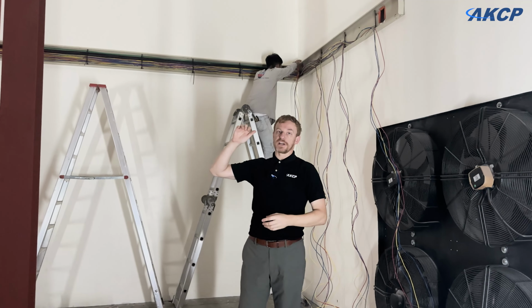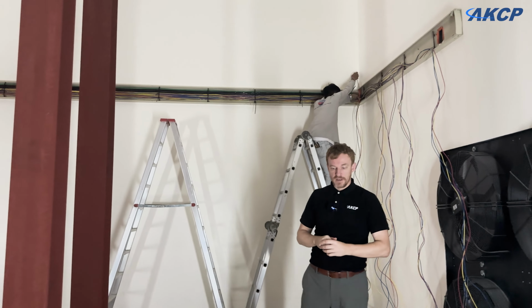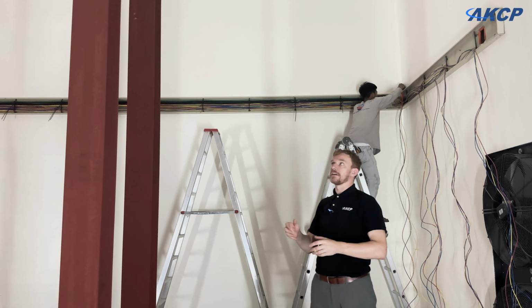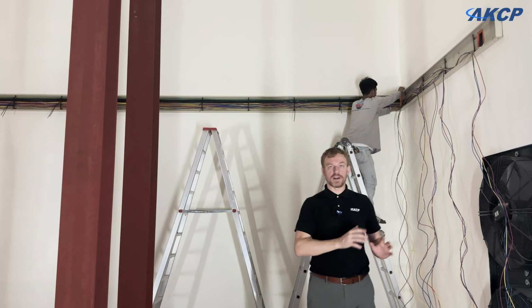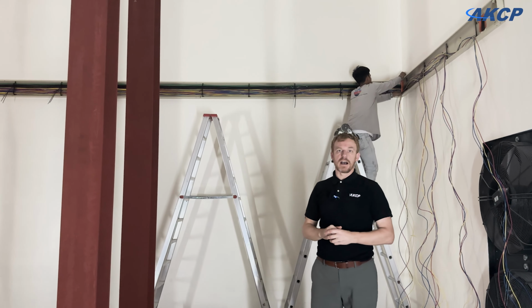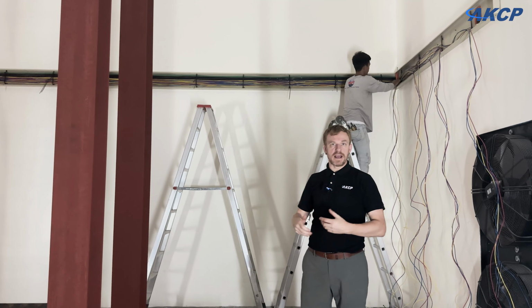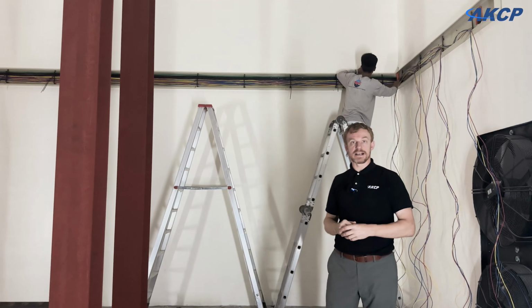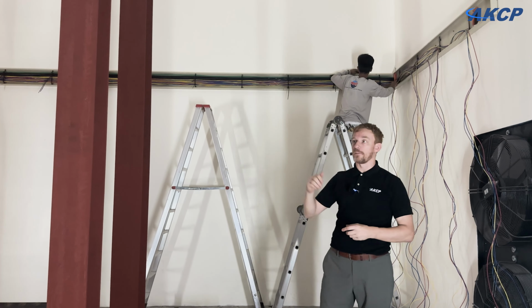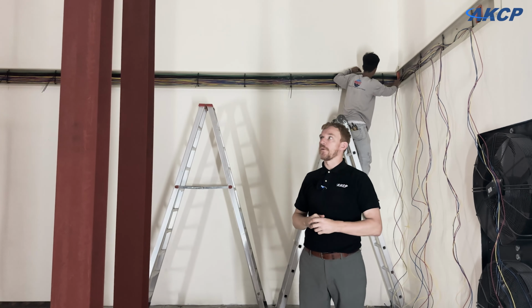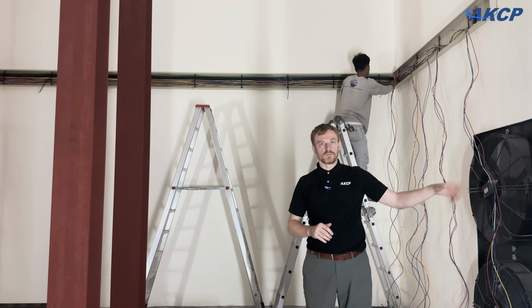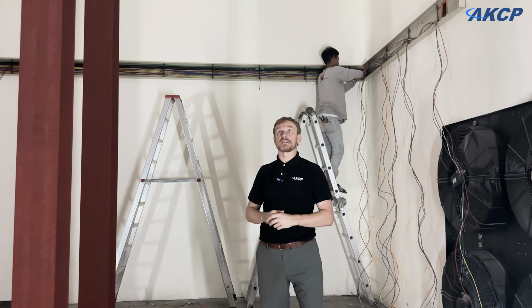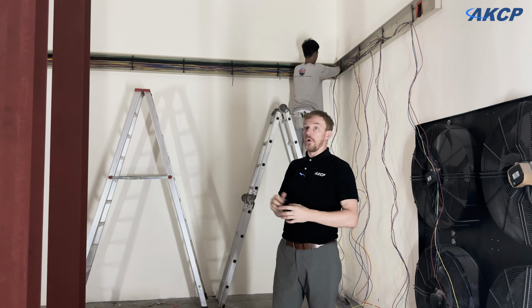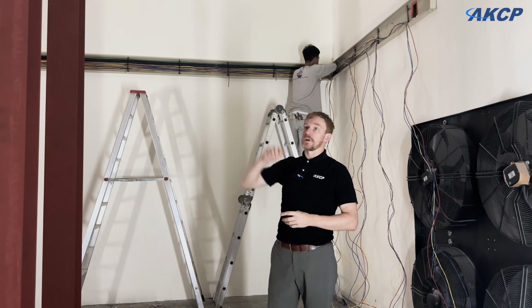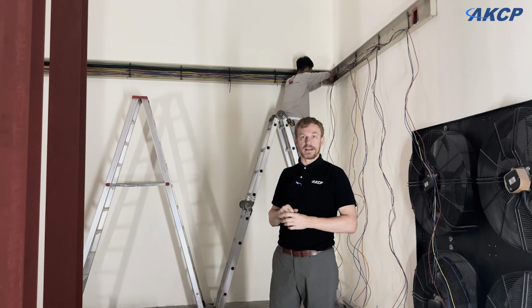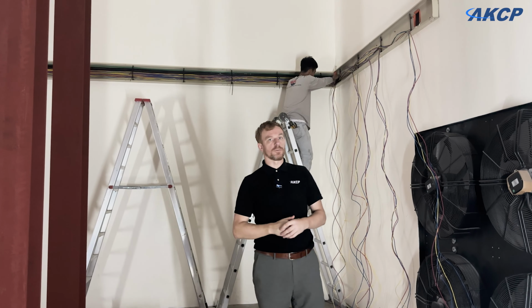The rooftop heat exchangers on top of this structure will operate either to pre-cool the air before it reaches the fan wall using our outside free cooler, an airside economizer, reducing the amount of cooling the fan wall has to do. Or if it's cold enough outside, the rooftop heat exchangers can provide 100% of the cooling and the fan wall could be turned off.